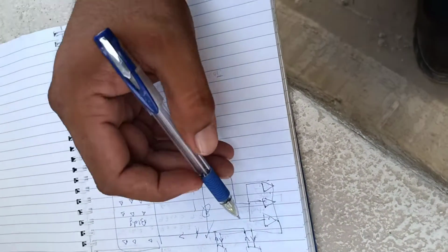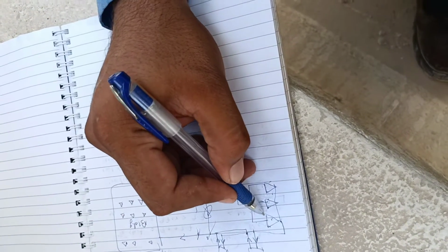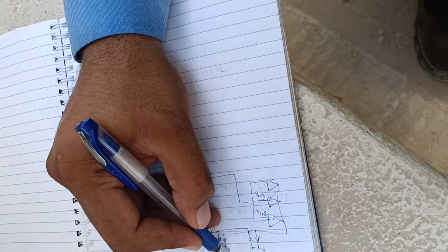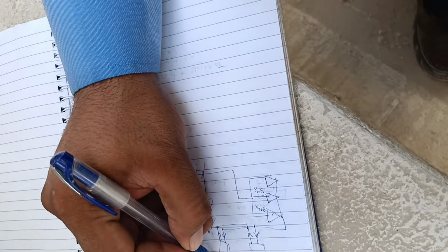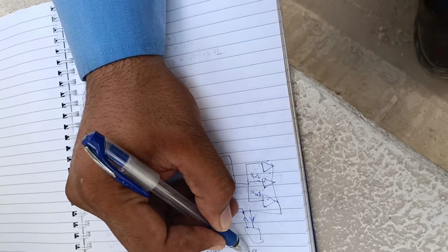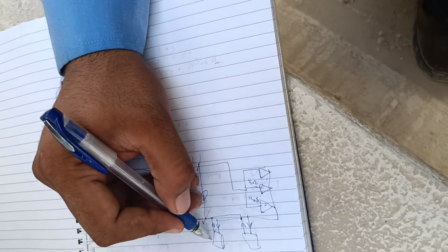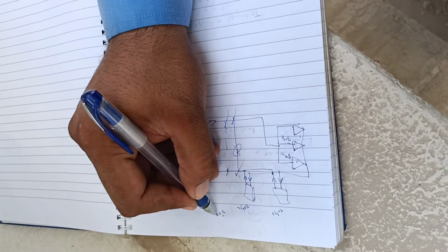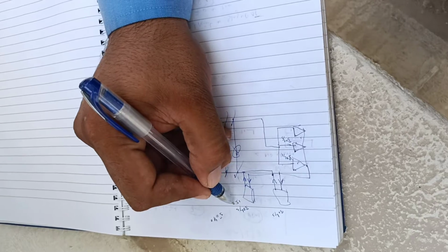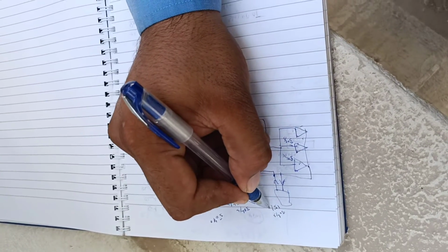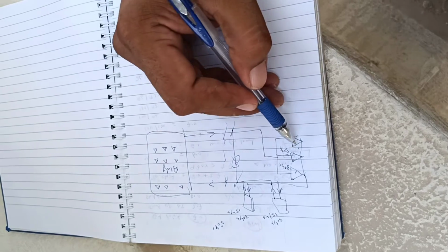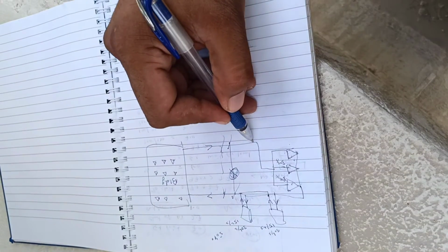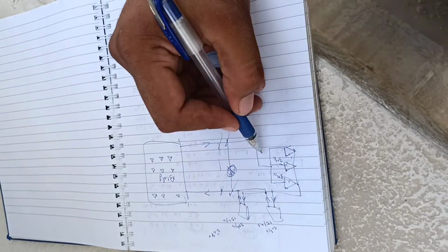So what will happen now? For example, you are running 2 pumps on, for example, 30 hertz. My chiller is designed on 30 liter per second. Now my chiller requirement for primary variable flow is minimum 50% of the flow. So I need at least 15 liter per second here always, right? Now these pumps are running on hand mode, this bypass valve is closed, and normally you are getting 60 liter per second.